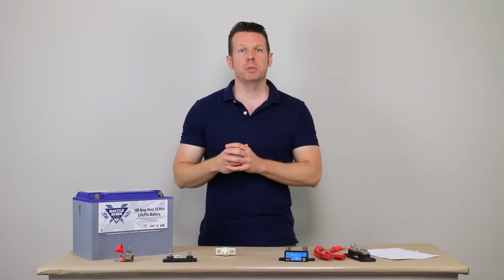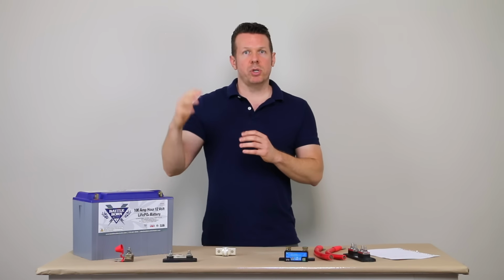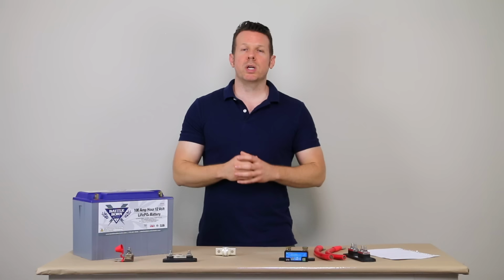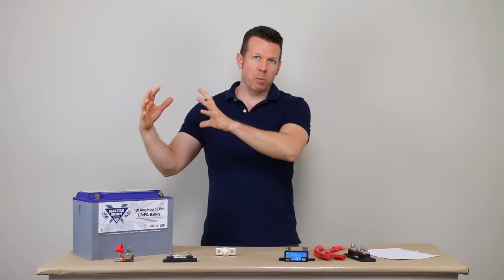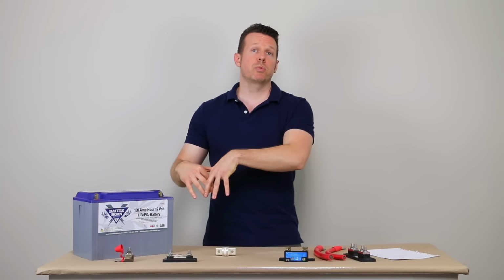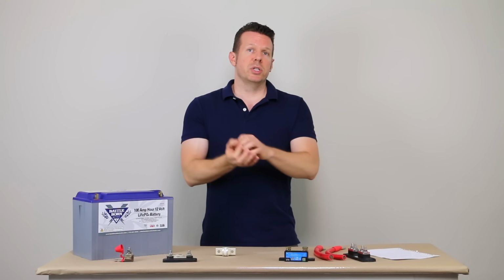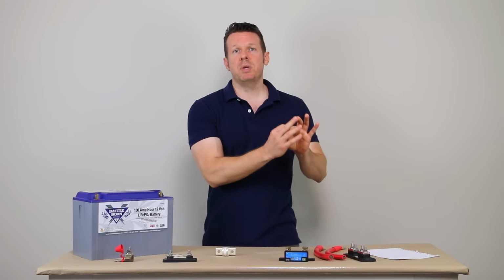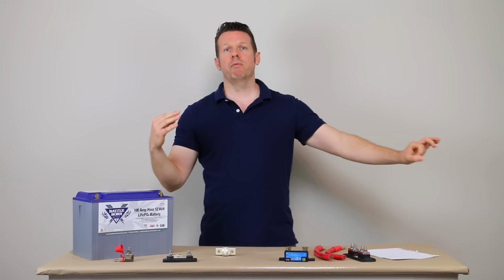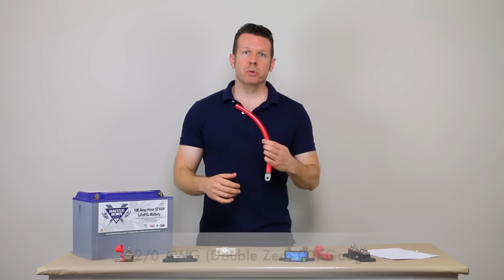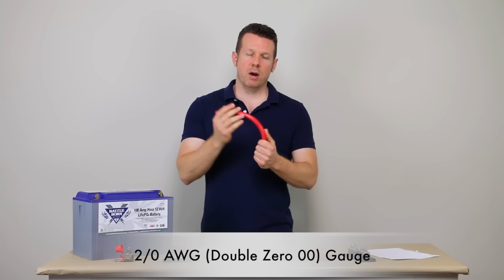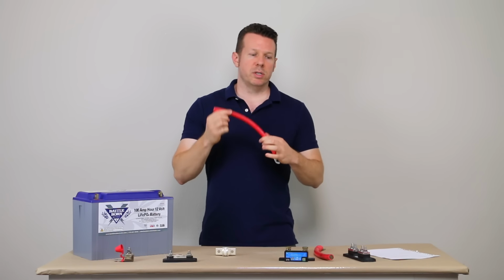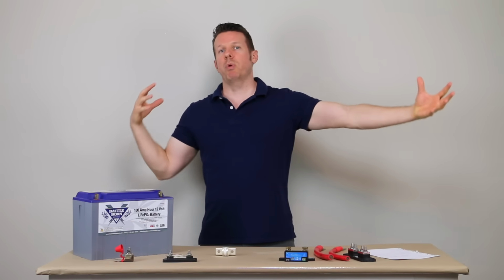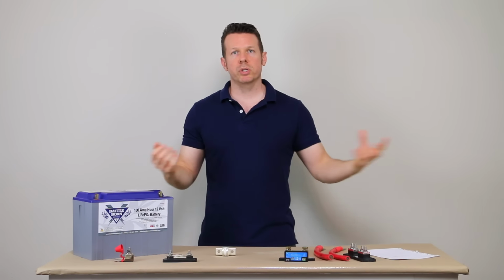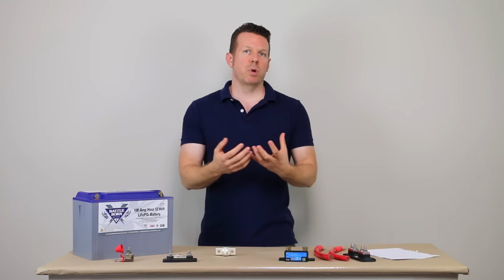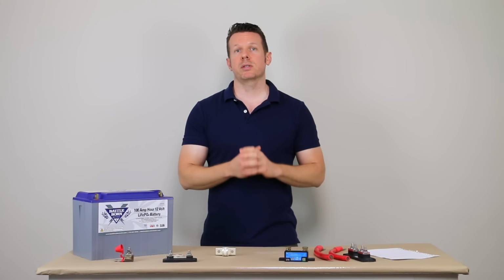He had a Victron Multiplus. The DC ripple, or the vibration in the system, we could call it, was so high that the alarm went off and the Multiplus inverter charger would shut down. This was caused by the cables not being thick enough for that 12-foot run. They were 2-aught cables, which is pretty large. This can carry 300 amps. I use this in a lot of systems, but over 12 feet, it was too much. The voltage drop was too high, and DC ripple is reduced when you increase the size of the cable.